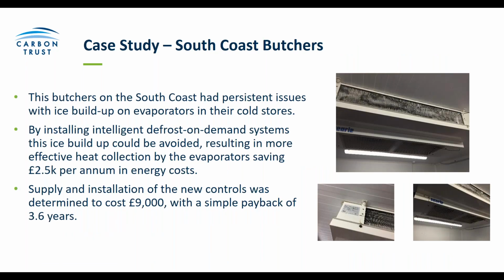A small business example: there was a butchers that we were in conversation with as part of the Green Business Fund, and we offered advice to them. They were on the south coast, and had persistent issues with buildup of ice on their evaporators. So they installed a defrost on demand system, which we mentioned earlier, which is basically an automated system, and it was able to save them £2,500 per year. With an initial outlay of £9,000, they were able to pay back the cost of that project in just over 3.5 years. So some considerable savings paid back pretty quickly there.